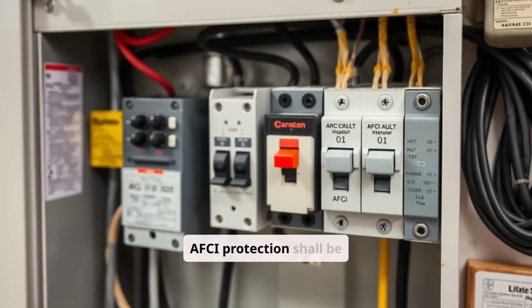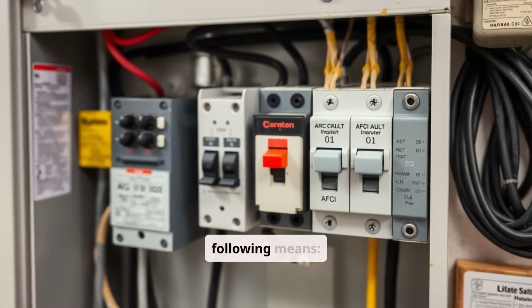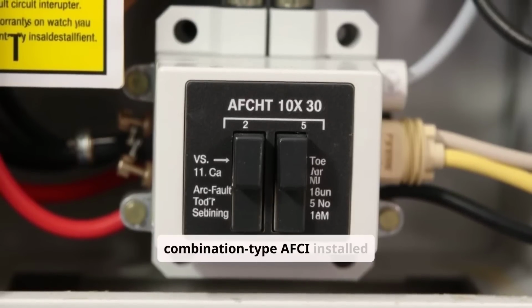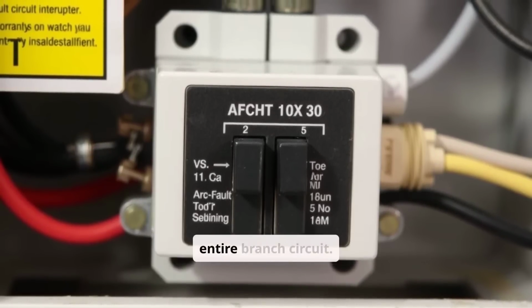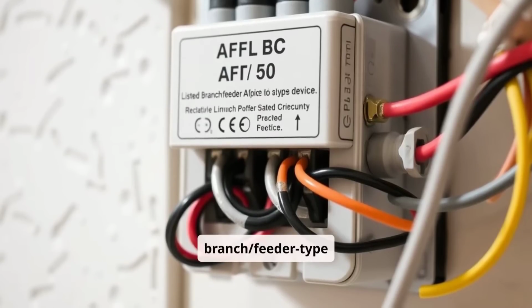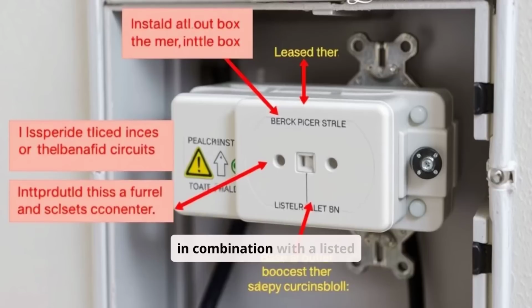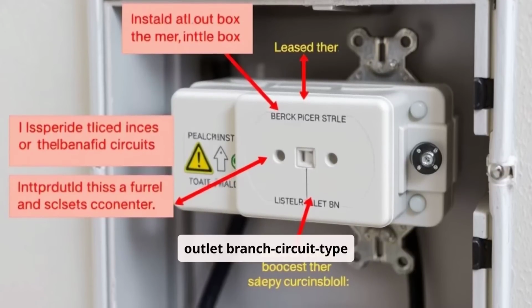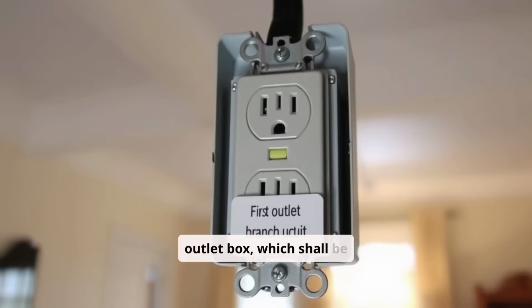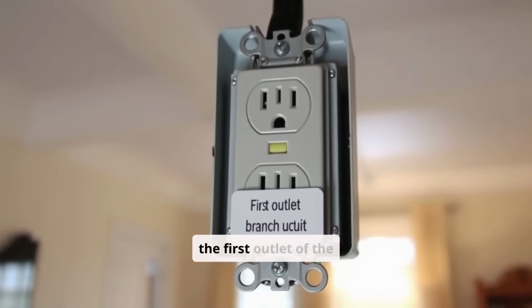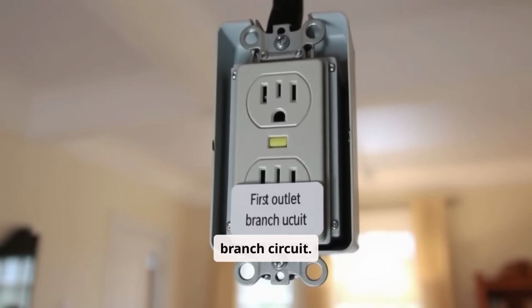Means of protection. AFCI protection shall be provided by any of the following means. 1. A listed combination type AFCI installed to provide protection of the entire branch circuit. 2. A listed branch/feeder type AFCI installed at the origin of the branch circuit in combination with a listed outlet branch circuit type AFCI installed on the branch circuit at the first outlet box, which shall be marked to indicate that it is the first outlet of the branch circuit.